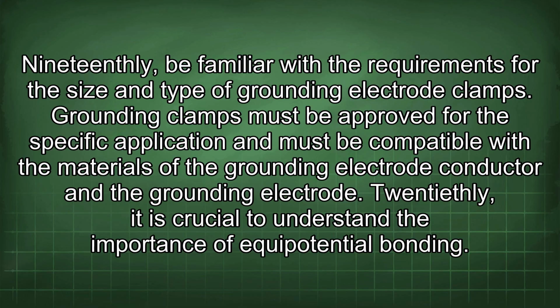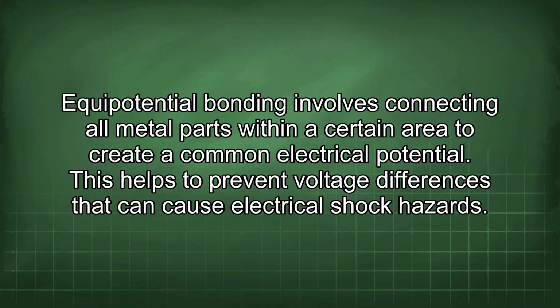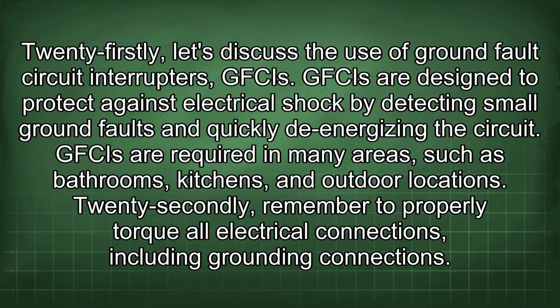20thly, it is crucial to understand the importance of equipotential bonding. Equipotential bonding involves connecting all metal parts within a certain area to create a common electrical potential. This helps to prevent voltage differences that can cause electrical shock hazards. 21stly, let's discuss the use of ground fault circuit interrupters, GFCIs. GFCIs are designed to protect against electrical shock by detecting small ground faults and quickly de-energizing the circuit. GFCIs are required in many areas, such as bathrooms, kitchens, and outdoor locations.